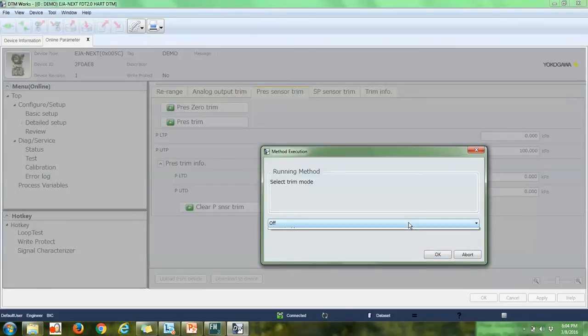So we've done our lower, so we've done a 0, and now we want to do our upper. Again, the transmitter is reading 0. Ideally, you would have a calibrator hooked up and a pump, and you would apply that 100% pressure a little bit higher, then look at what it's reading up here, take the calibrator value and put it down here. That's how you would make that higher trim adjustment. I don't have a calibrator hooked up right now, so I'm going to go ahead and abort this, but it would be a similar process to the lower trim.